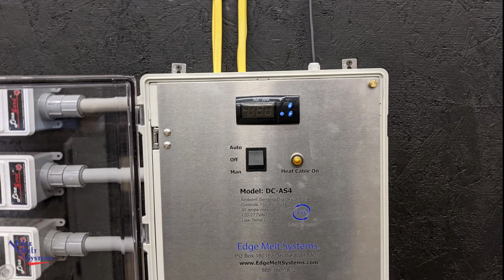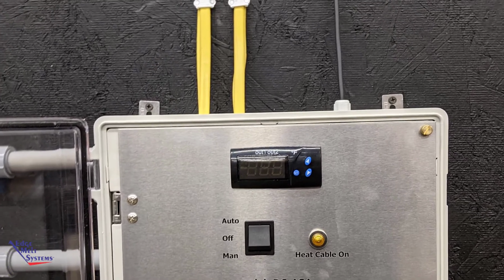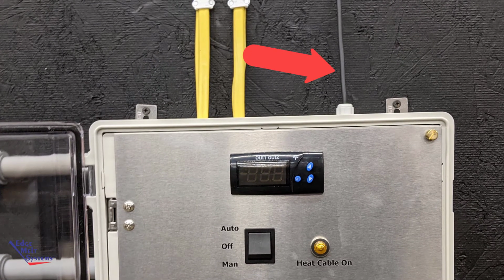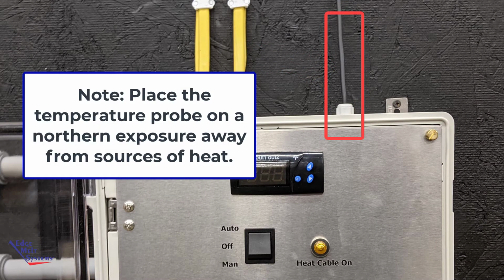Here's an example of incoming and outgoing power. There are no knockouts provided in the enclosure, so you're able to tap in at any point. As indicated, we see on the side with the EPD units coming in, line and load going out, and then as well pictured is the non-polarized temp probe lead wire that extends to the outside.